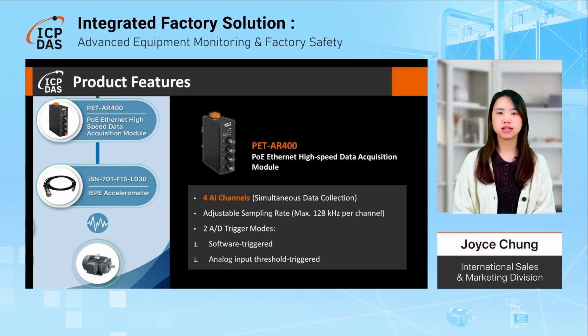The PETAR400 Ethernet high-speed data acquisition module provides 4 analog input channels and enables simultaneous multi-channel data acquisition. Its sampling rate is adjustable, with the maximum of 128 kHz per channel. Additionally, it supports 2 A/D trigger modes, software-triggered and analog input threshold-triggered.